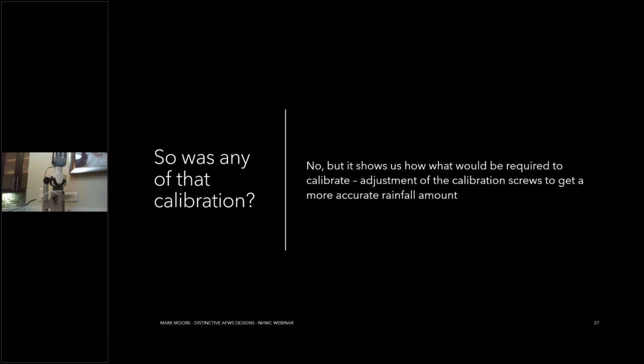So I've given 2 examples on my webcam, what I call a static calibration and what I've done so far is a dynamic calibration, but I haven't actually calibrated it. I haven't adjusted the set screws to make it more accurate. The true full calibration would be looking at the error from both a static and a dynamic test, adjusting those set screws, retesting it, and getting that error as close to 0 as possible. That would take 30 minutes to an hour for just one tipping bucket, depending on how well it was behaving. So we're not going to do that for this presentation. But I just wanted you to see the steps that would take. We'd get our error, and then we would adjust these screws to make it more accurate if need be.